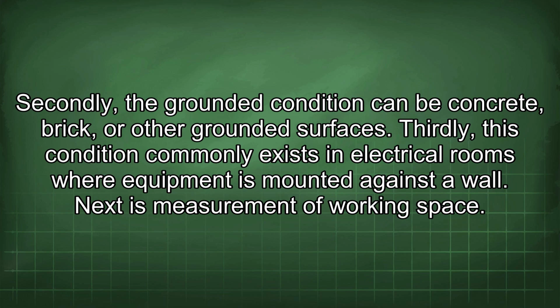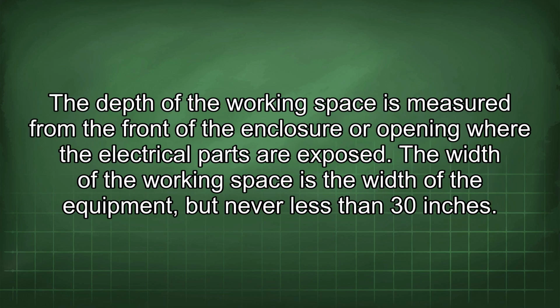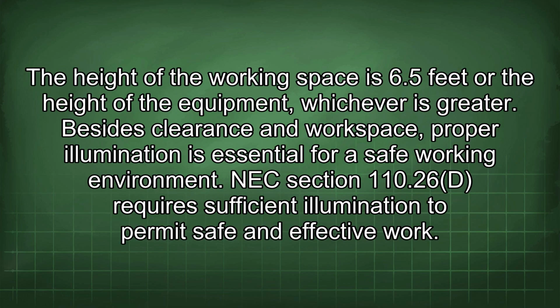Next is measurement of working space. The depth of the working space is measured from the front of the enclosure or opening where the electrical parts are exposed. The width of the working space is the width of the equipment, but never less than 30 inches. The height of the working space is 6.5 feet, or the height of the equipment, whichever is greater.